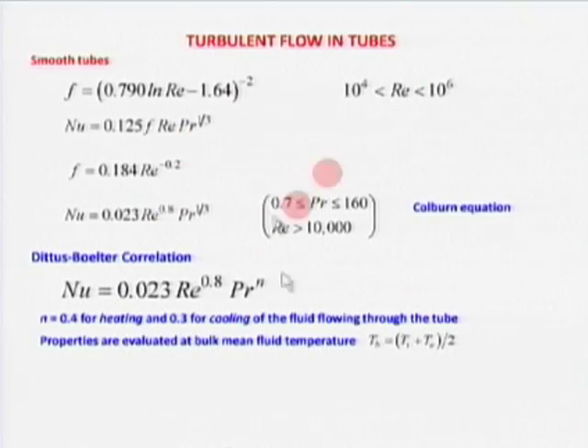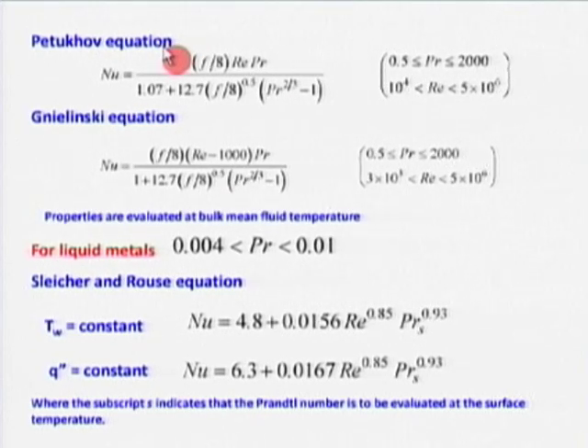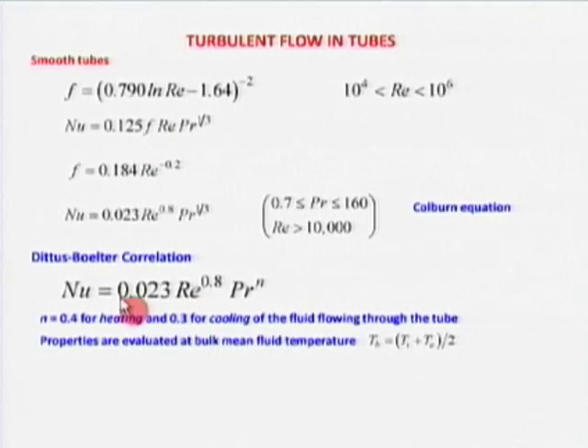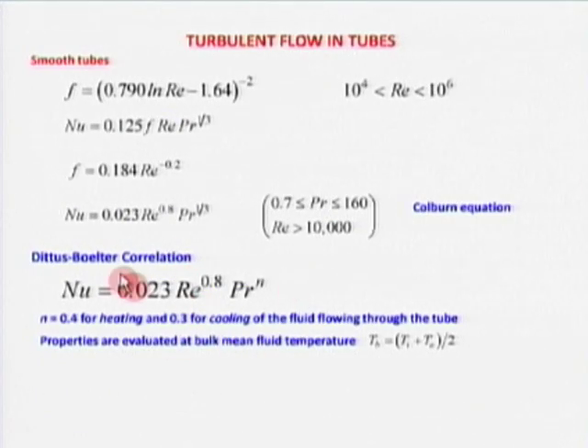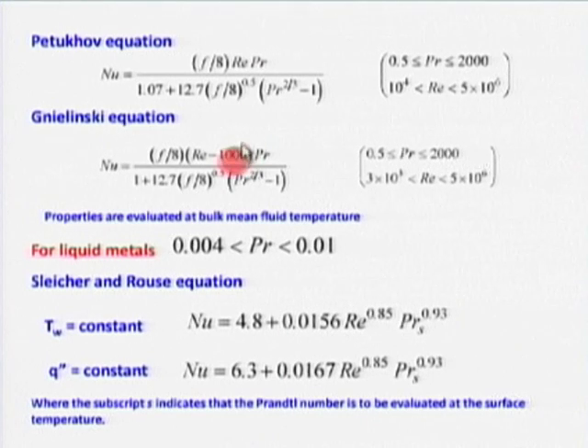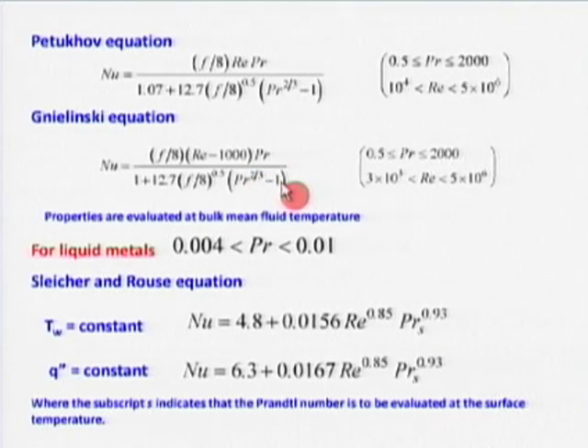We have stated correlations for both laminar and turbulent flow in pipes. Another important correlation is the Gnielinski correlation. Dittus-Boelter works well for gases, while Gnielinski works well for liquids. This was learned the hard way — when measuring for water, Dittus-Boelter never matched well, but Gnielinski gave correct results.